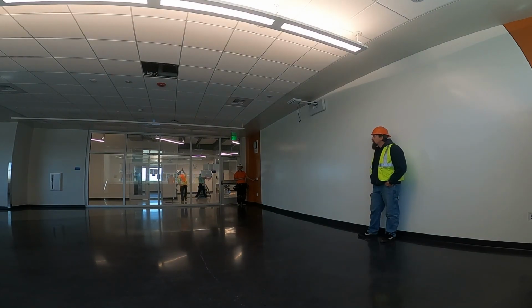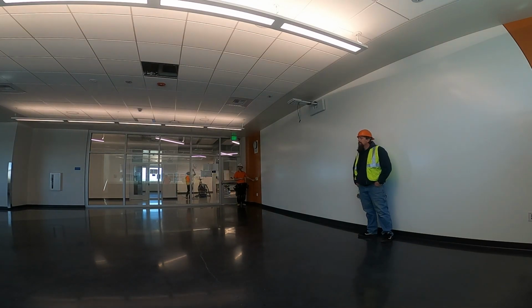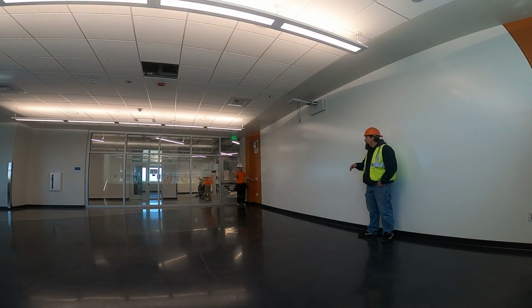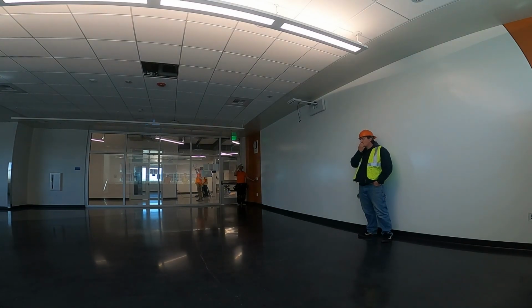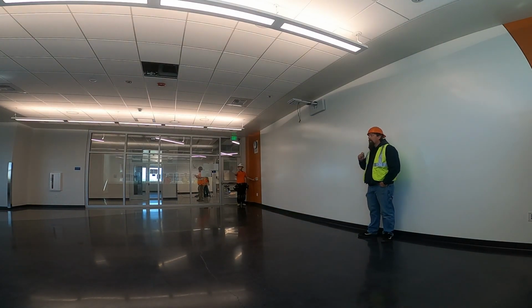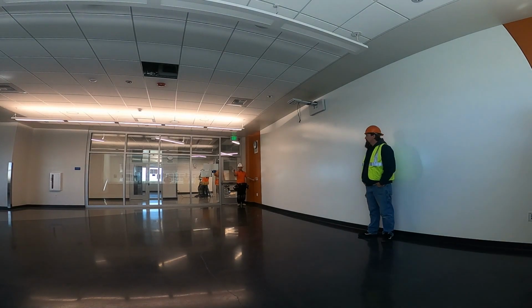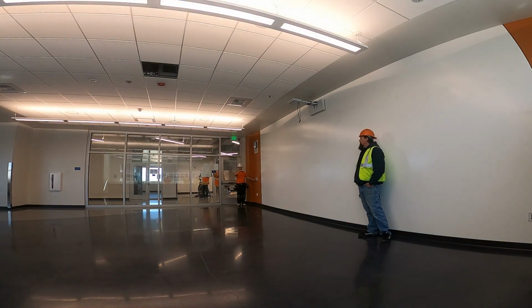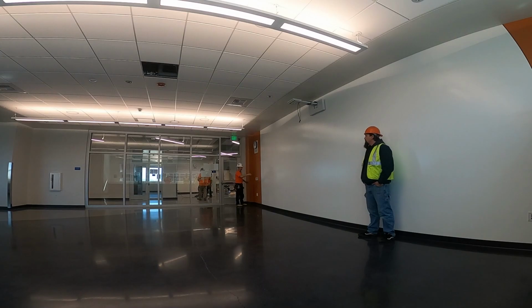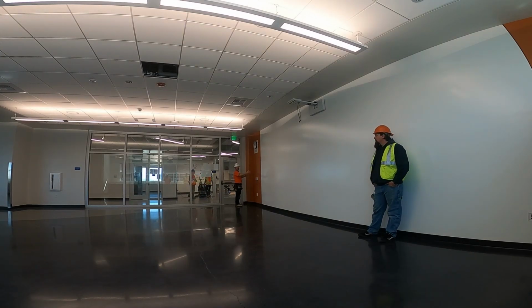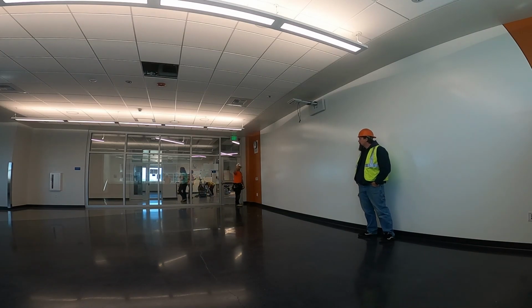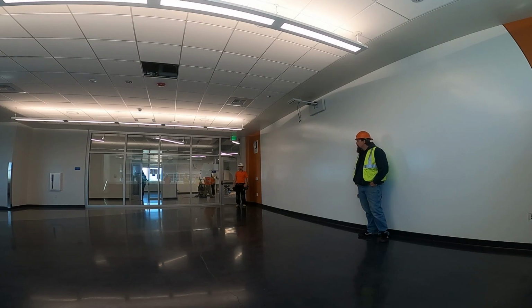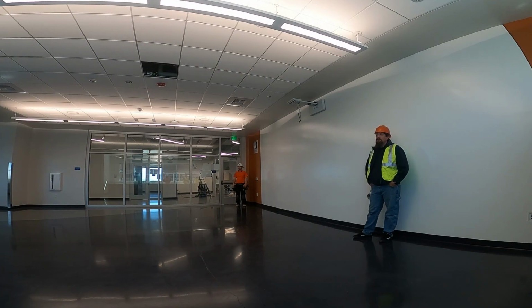And the way the room controllers come, zone 1, which is that one, is going to be your primary daylight zone. This is zone 2. And the way these are set up on the plans, for the most part, zone 1 is always on the right as you're facing the screen. So it's different over there - if you look at A and B, over there the right side is A and that side is B. So I don't know, maybe that's just lazy engineering, copy and pasting.